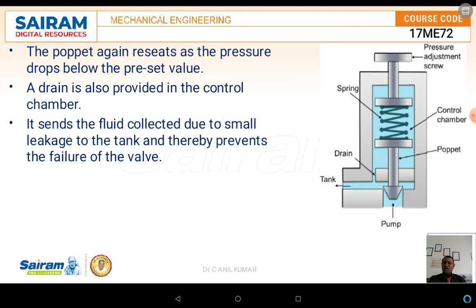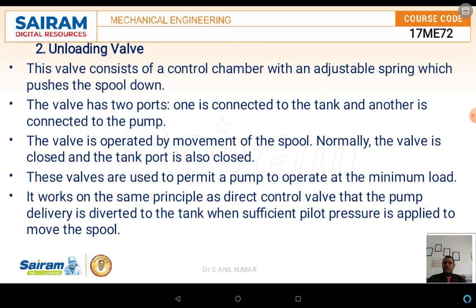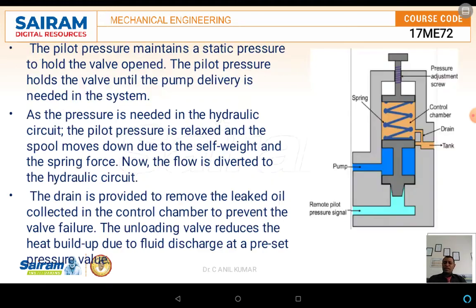The next type we are discussing is the unloading valve. The unloading valve is another type of valve. It consists of a control chamber with an adjustable spring which pushes the spool down. This valve has two ports: one is connected to the tank port and another is connected to the pump port. The unloading valve consists of an inlet port which is the pump port and another which is the tank port. The movement of the spool takes place because of the spring pressure.